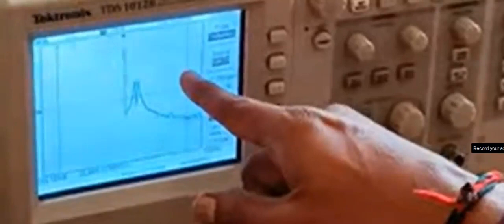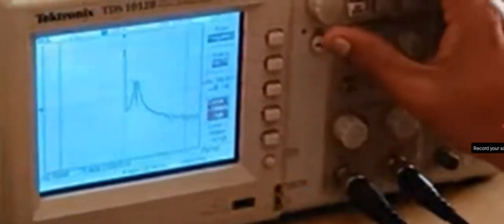Whatever the two cursor points—this is one and this is another one. Right now, this is a dashed line, this is a solid line, so cursor 1 is selected. I will use this knob to fix the cursor location. You can fix the cursor location at this point.